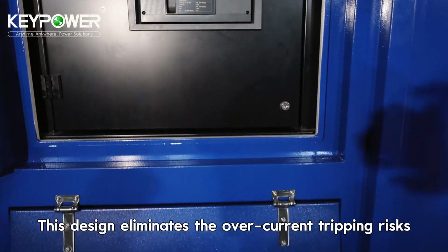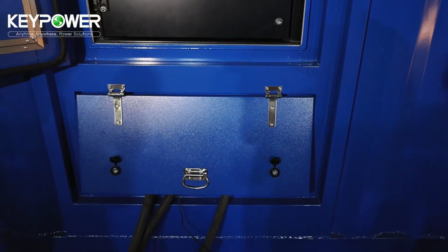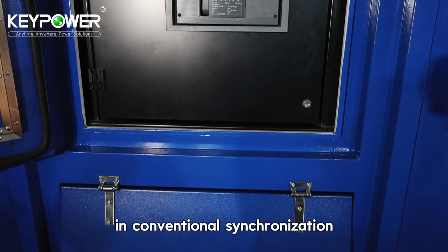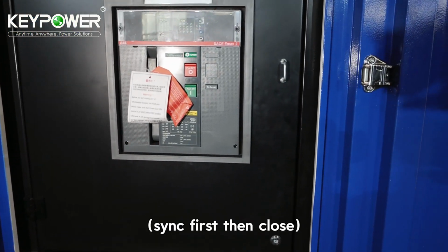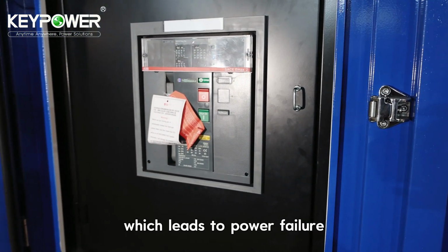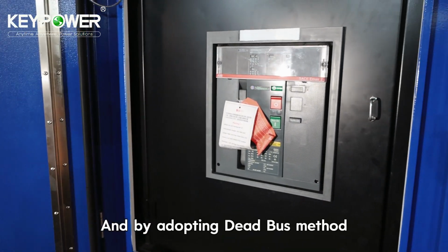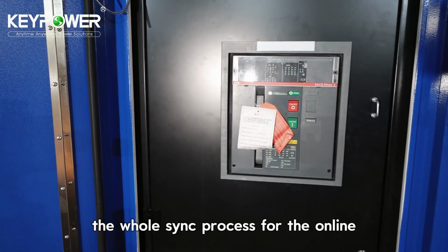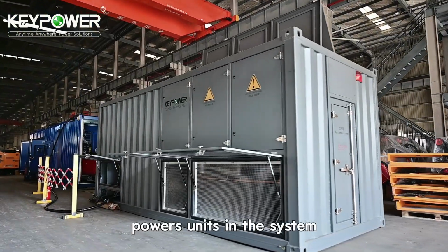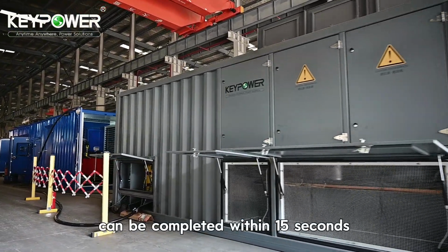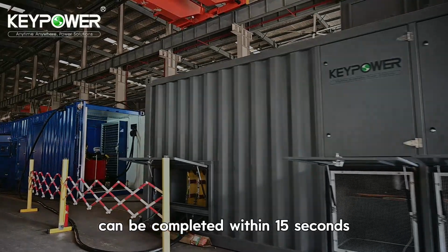This design eliminates the overcurrent tripping risks during breaker closing in conventional synchronization, which syncs first, then closes, and which leads to power failure. And by adopting the dead bus method, the whole sync process for the online power units in the system can be completed within 15 seconds.